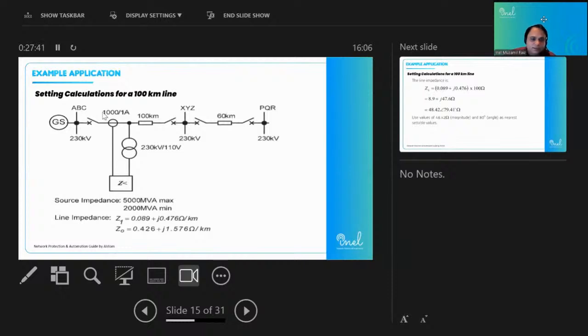So now we'll take an example of a typical transmission line, which is 100 kilometers in length, and this is a generating station. This is bus bar ABC, which is at the 230 kV level, and this 100-kilometer line ranges from point ABC to point XYZ. Now we need to calculate settings. So this is the source impedance, which is 5000 MVA max at this point. And this source impedance means this is the short circuit level at point ABC. During the maximum fault level condition, 5000 MVA will be there, and during the minimum fault level condition, 2000 MVA will be there. Now we have the source impedance.